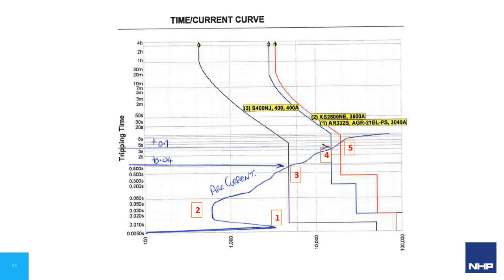Then if that tool vaporizes, it turns into an arc fault. Immediately you've got a much higher impedance than the short circuit that originally started off the event. So the current will drop to point number two, and then slowly increase as that arc develops and more arc gases are created, and eventually the current climbs up into a region where the trips start to occur. You can see that even on this theoretical 400 amp molded case breaker, you could still be tripping out in a significant amount of time, about half a second. But if it happened to be further up towards points 4 and 5, that's getting into seconds of tripping time, which is an eternity in electrical terms.